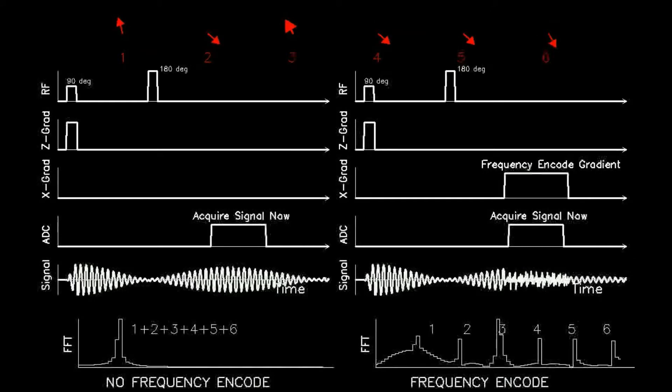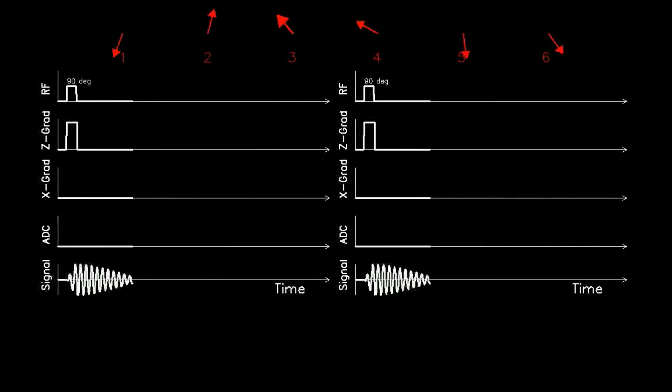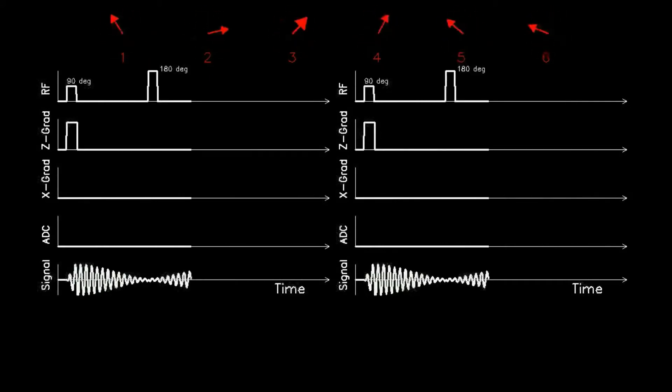The second timeline shows application of the Z gradient required for slice. The third timeline shows the application of the frequency encoding magnetic gradient along the X or horizontal direction. The fourth line shows the time window when signal is required for image formation, and the bottom line shows the entire signal.